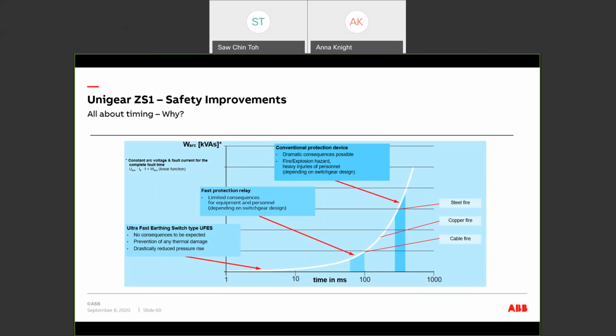To limit the risk, we can consider including active protection to limit the energy created. As you can see, speed and time are very important in such a situation, and a millisecond actually means a very different outcome. The idea is that the more we can limit the internal arc energy, the better it is for asset and human protection. By using light sensors together with the protection relays, we can limit the fault to around 100 milliseconds. And by using an ultra-fast earthing switch, UFES, we can further reduce the time to around 4 milliseconds, protecting the site as well as the operators.